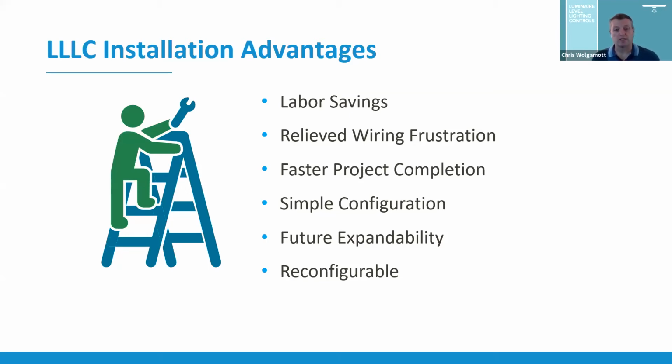And the nice thing is also that you can add to these at a later date. You can do small sections of your building and move on and do other pieces, and it just connects up in a relatively easy manner. Or as you move on, if you decide that your open space needs a few more closed offices, the reconfiguration is even easier because you don't have to rewire stuff. You don't have to worry about a single sensor that's driving multiple fixtures and having to rewire that or put a new sensor in, because you can disconnect and reconnect all the fixtures wirelessly and through the app.